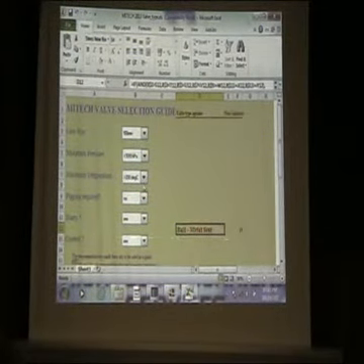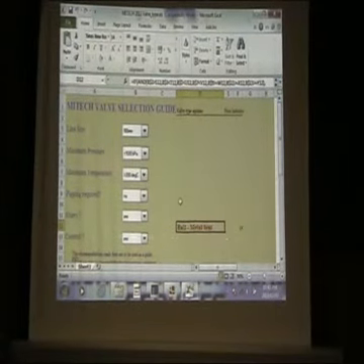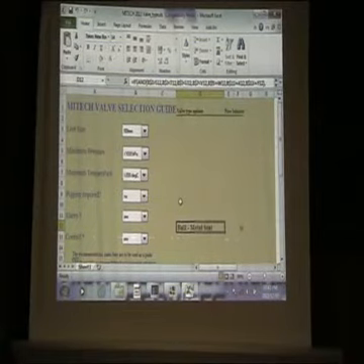So what are they saying? On this application, if you want to specify to your valve guy, you'll tell him, I want a metal seated ball valve for control, yes, more than 200 degrees, less than 1000 kPa, and it's 100 millimeter size. That's just an indication for you guys to more or less decide what type of valve you want to use.